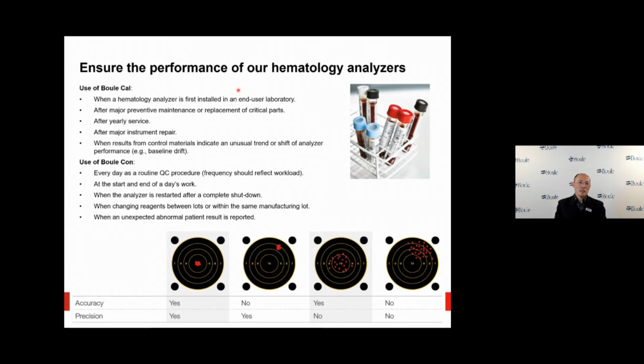Calibrator blood is a highly accurate blood with a shorter shelf life and shorter open-vial viability. Calibrator blood is produced 8 batches per year to make the analysis result as accurate as the assay sheet. So when the instrument needs calibration, the calibrator blood is needed.